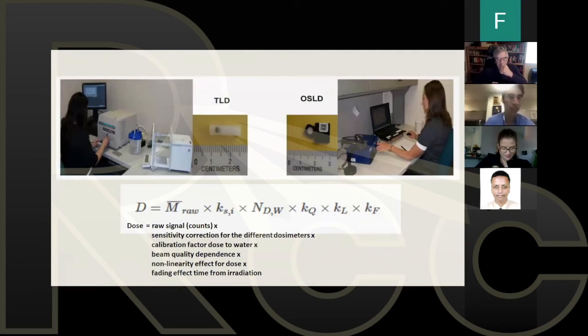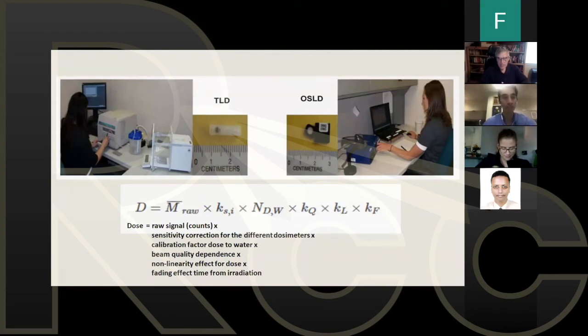And then the last question is, is the TLD that you were showing used for all energies or just some energies? And Tia responded that the TLD can be used for all energies, but they do need to be calibrated. Yes. And the slide that I have up there shows that there is a beam quality dependence factor right here, KQ, which corrects it for the different energies.